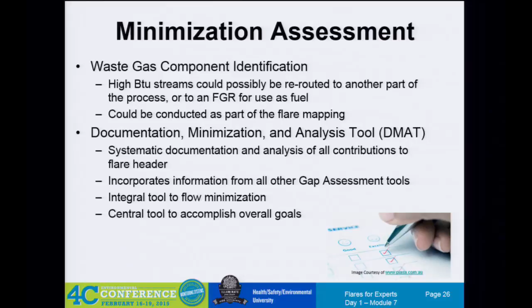Another thing to look for is high H2S streams. If you have high H2S streams going to your flare, look for ways to get rid of those first. The last thing you want to do is remove a bunch of low sulfur, high volume streams from your flare, because remember, you're on a 162 ppm concentration limit. Don't create a concentration problem where there isn't one - get the H2S out first, then go after flow.